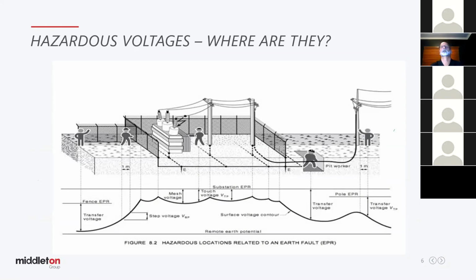Okay, so I'm not sure, you probably see my cursor. This is a typical switch yard, and we can see we've got a fault on the transformer across the bushing there. So now we've got an earth fault on this switch yard. And as we know, there'll be a resistance of the grid here. We push current through it, we create a voltage. And that voltage at the switch yard is known as our EPR, or earth potential rise.